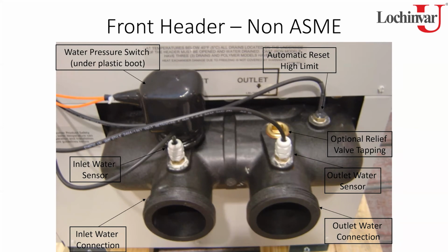You've got your water pressure switch back there. That's your standard water safety device that's set at 5 PSI as it leaves the factory. If you want to use some other safety, such as a flow switch in conjunction with this, that's perfectly fine. You can wire that in as an auxiliary safety, so you do have that ability. And then over here on the back side, you have your automatic reset high limit, which is basically monitoring the temperature coming out of those tubes, so we make sure it doesn't get too hot coming out at that point. So these are our connections on the non-ASME.